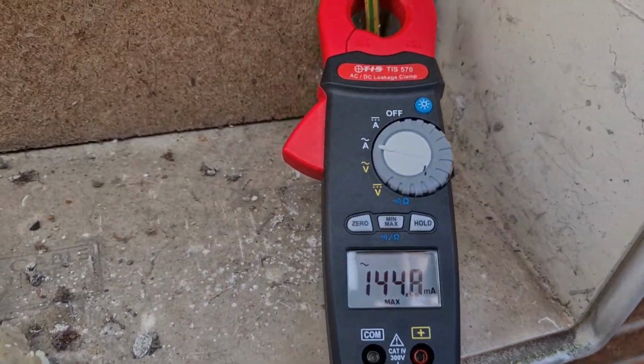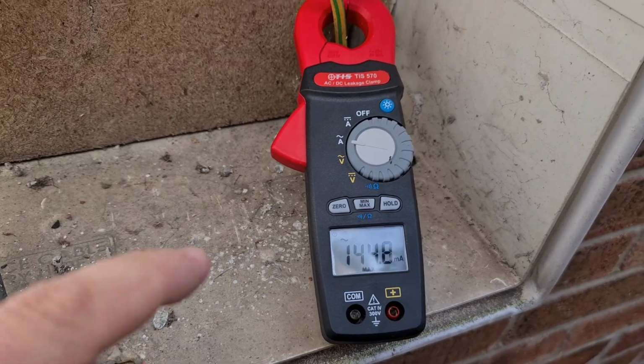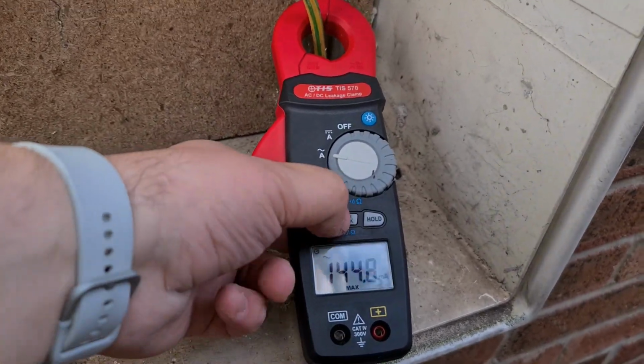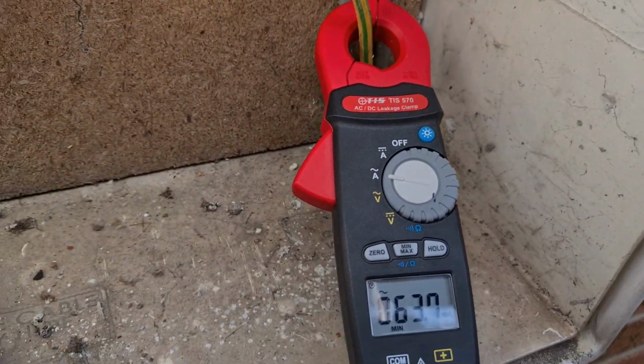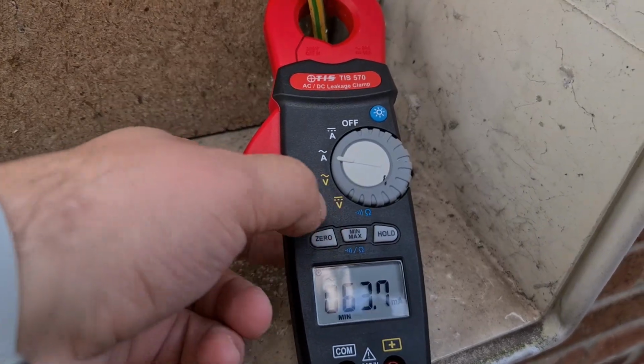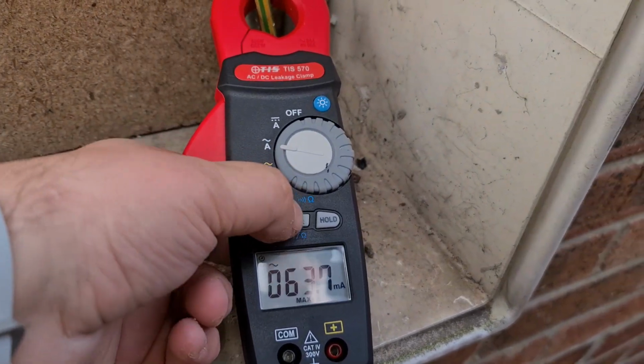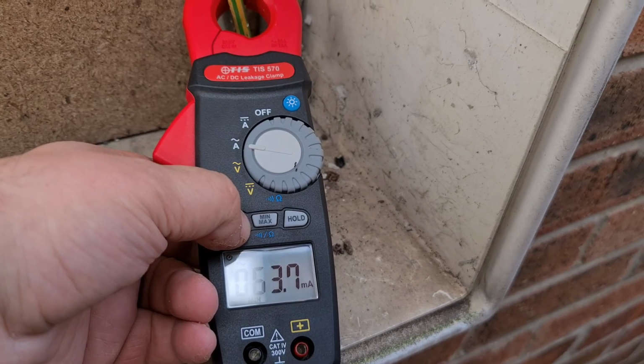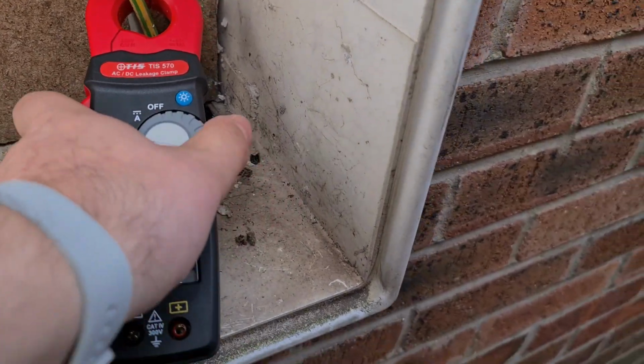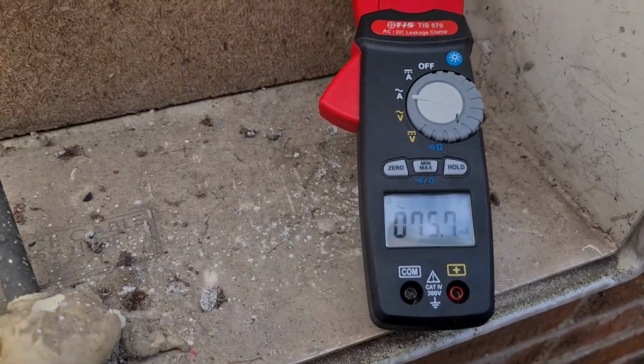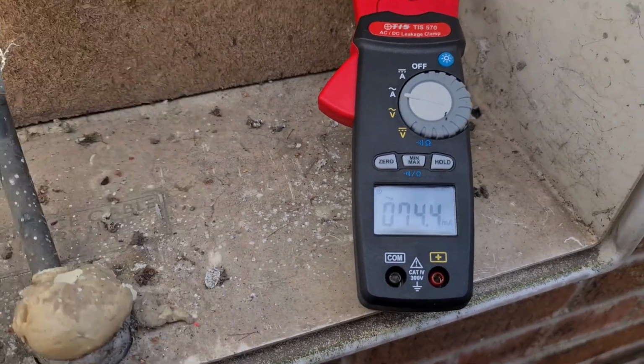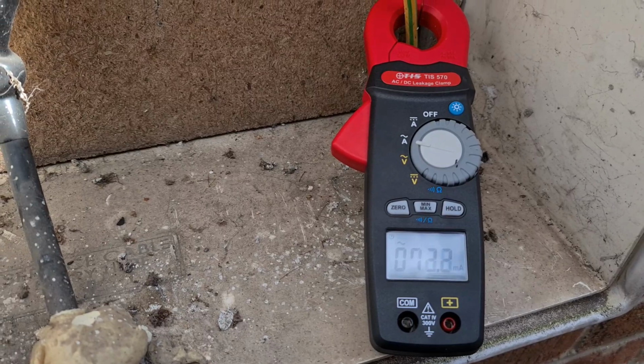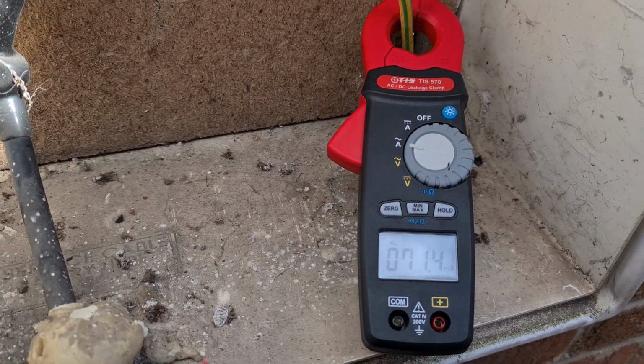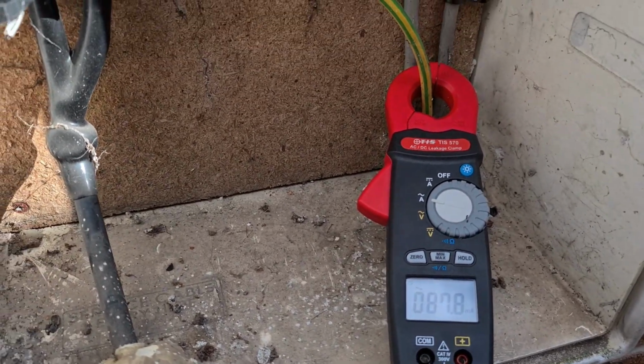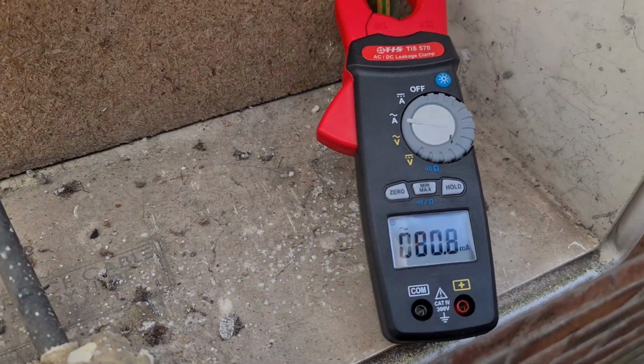So you can see through all the time I've been messing about on this system, that's its maximum, and its minimum is down at 63. If I clear that off now, I'm sure there would be a way to do that, but I've just switched it off and on again because I'm a heathen. And you can see there it's sort of around 70, 75 at the minute. So yeah, it's just interesting to see what can actually be flowing through an earthing system.